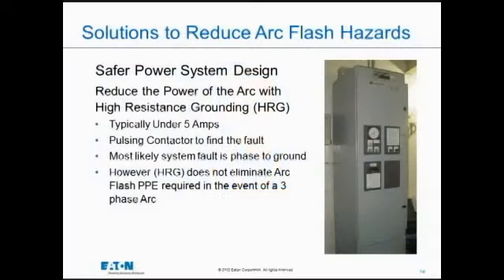But for the rest of the power system that only needs 3-phase 3-wire, we put a resistor in the neutral of the transformer and restrict the current to something like 5 amps. Very low amount of current, very low spark, very minimal, not a concern for skin burns, other than the tip of your finger, I guess, if it was close to the arc. That's like pulling the plug out of the wall socket when the iron is on type of arc. So this is good design, and it certainly increases system reliability as well.